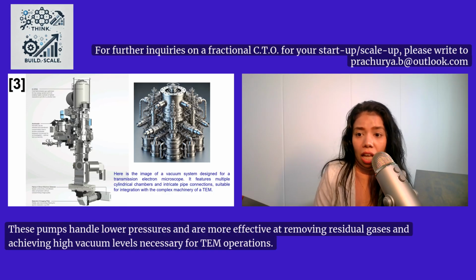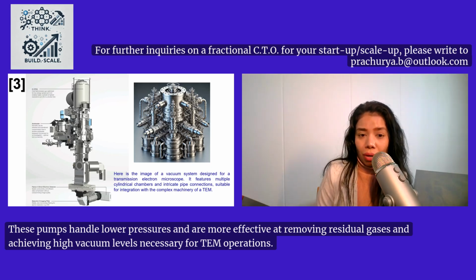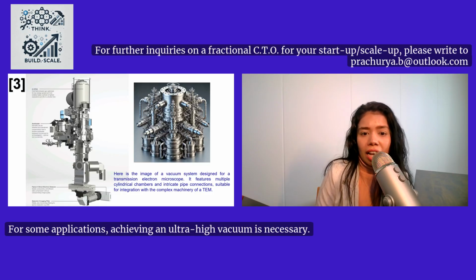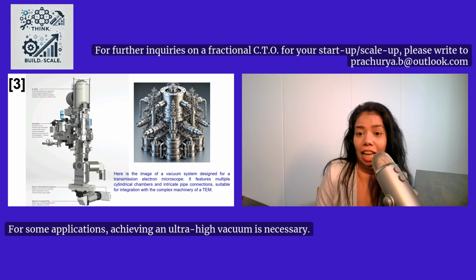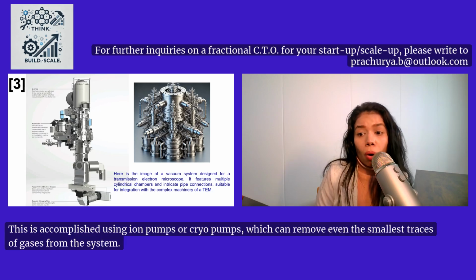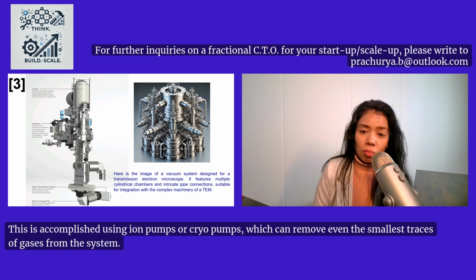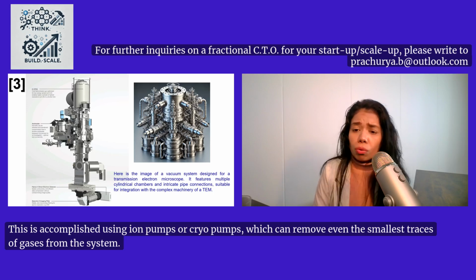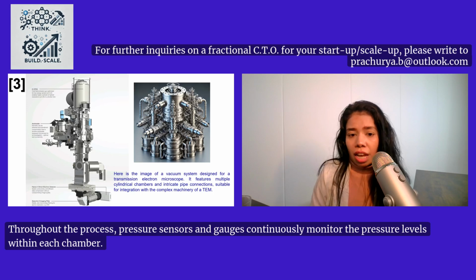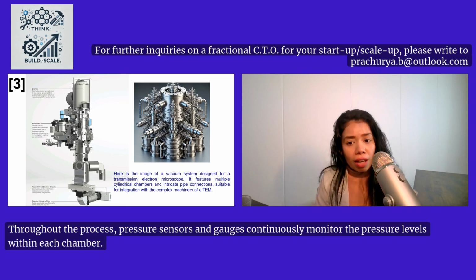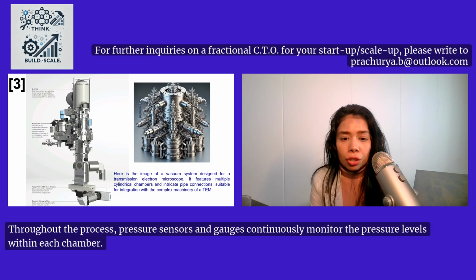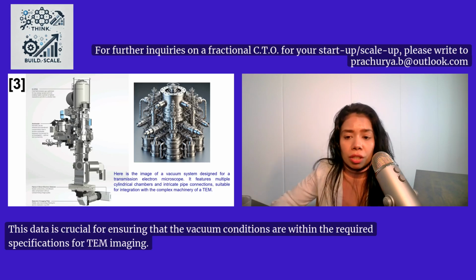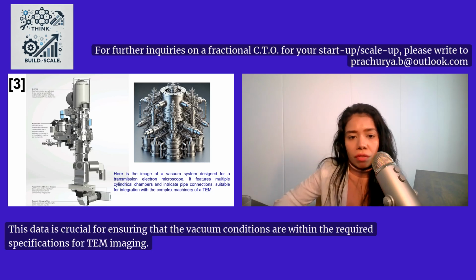These pumps handle lower pressures and are more effective at removing residual gases and achieving high vacuum levels necessary for TEM operations. For some applications, achieving an ultra-high vacuum is necessary. This is accomplished using ion pumps or cryopumps, which can remove even the smallest traces of gases from the system. Throughout the process, pressure sensors and gauges continuously monitor the pressure levels within each chamber. This data is crucial for ensuring that the vacuum conditions are within the required specifications for TEM imaging.